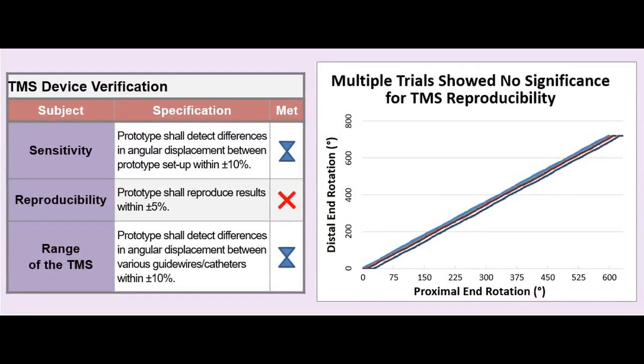To test the reproducibility of the TMS, 9 trials were conducted in the pathway 3 configuration, and the angular rotation was obtained. When comparing the linear regression lines using the ANCOVA analysis, all trials were significantly different from the ideal 1-to-1 ratio, which has a p-value less than 0.05. This failed to accept the null hypothesis, meaning the TMS failed to reproduce angular rotation results between the trials within the required specification. More tests were required to identify a potential solution to improve the reproducibility of the system.